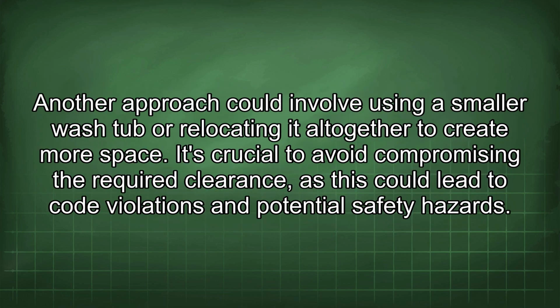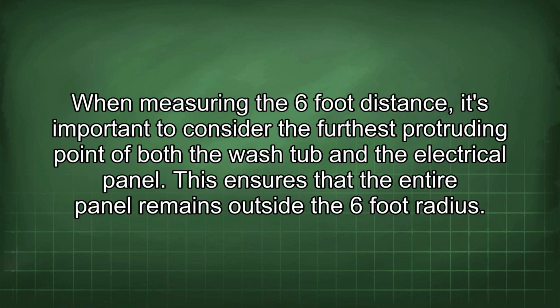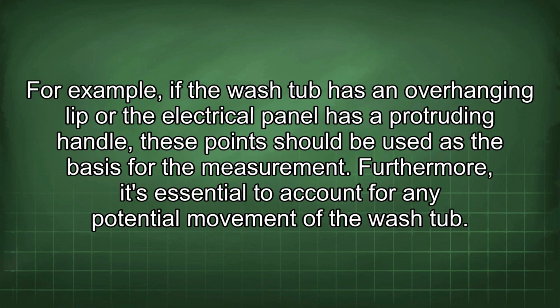Another approach could involve using a smaller wash tub or relocating it altogether to create more space. It's crucial to avoid compromising the required clearance, as this could lead to code violations and potential safety hazards. When measuring the 6-foot distance, it's important to consider the furthest protruding point of both the wash tub and the electrical panel. This ensures that the entire panel remains outside the 6-foot radius. For example, if the wash tub has an overhang lip or the electrical panel has a protruding handle, these points should be used as the basis for the measurement.